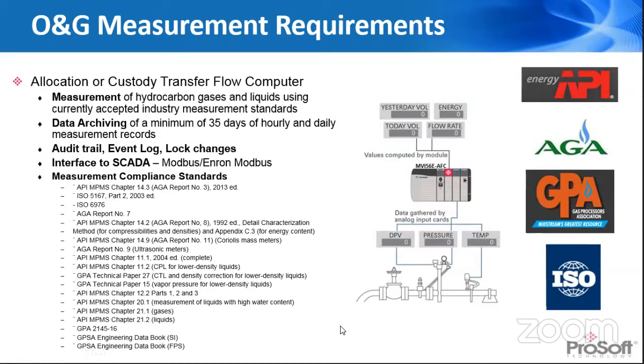But when you talk about measurement-related requirements, there are some very specific functions that are required, and that's why you're not able to necessarily do that directly in a Rockwell PLC. When we talk about measurement, there are things that the API requires, such as archiving a minimum of 35 days worth of history, both hourly and daily history. They need to have an audit trail. So if any parameter gets changed that can change the measurement, like if somebody comes out and changes an orifice plate or changes a meter factor or a K factor, you have to have an event log that keeps track of who made that change, what time it was changed, and what they changed it from and to. So if they change from a 5-inch orifice plate to a 6 1/4-inch orifice plate, that has to be part of an audit trail.